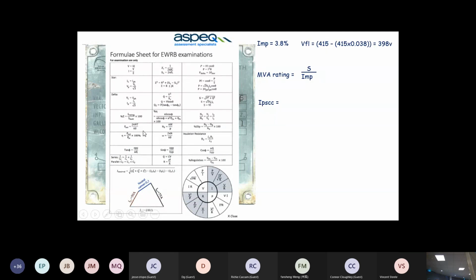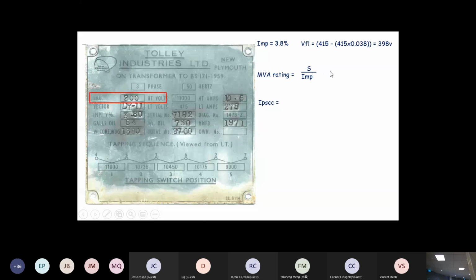Right, and look at this formula sheet. There is your formula. Now all it says is S rating, S fault, impedance. Now that formula, transpose it, it's the same as that. Now all I want to share, what is S? S is your 200,000. Can anybody tell me what's the impedance? How many percent? 3.8%, which is 0.038. There we are. This transformer has got an MVA rating of 5.26. So if there's a dead short, your kVA is going to go from 200 to 5.26 million.